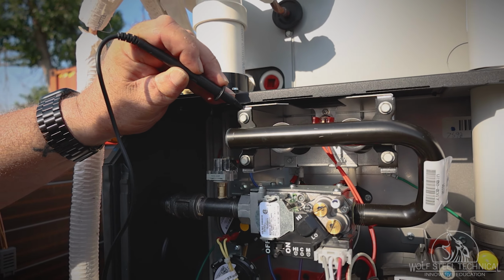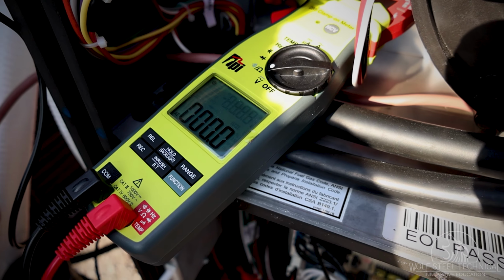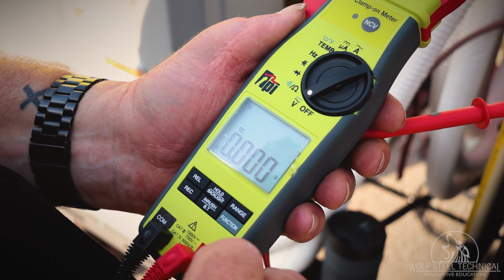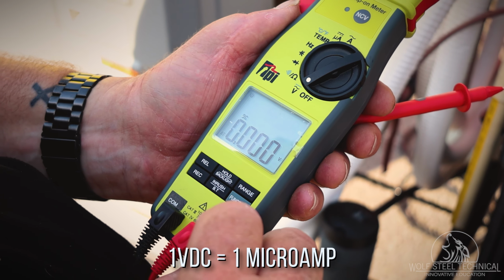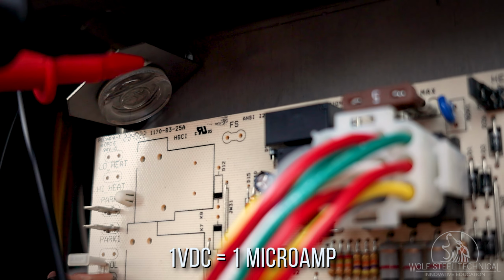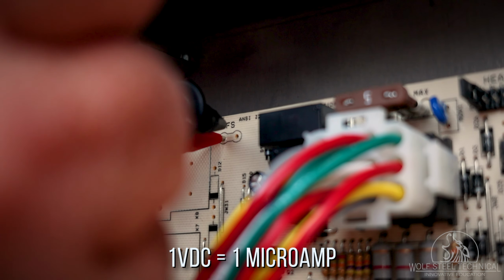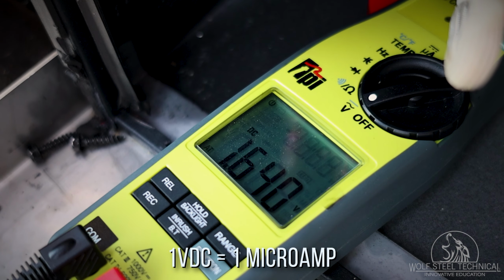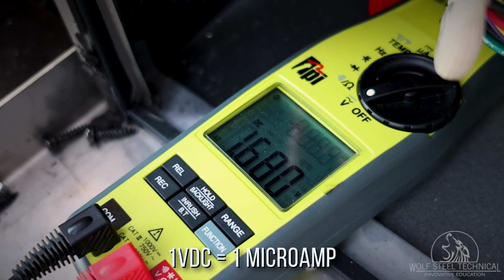Touching the leads to the burner box and the ground should result in a 0 reading. Once there is a flame that does not drop out, switch your multimeter to volts DC and check the flame current test port located on the right-hand side of the board. This should read between 0.5 and 3 microamps.